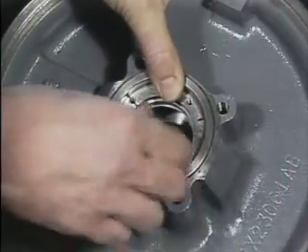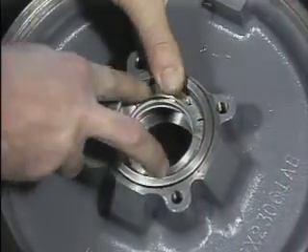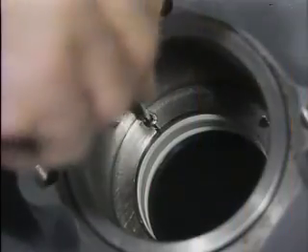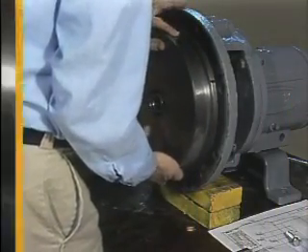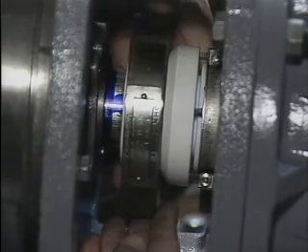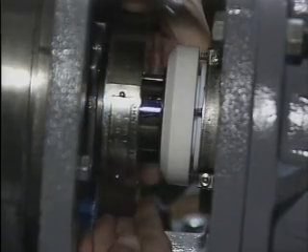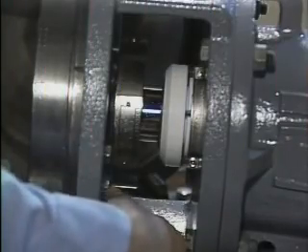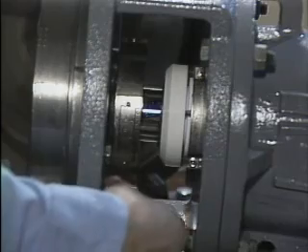Now the back plate is prepared for installation. First, the bushing is inserted into the stuffing box and secured with a screw. Then the back plate is installed on the pump frame. Next, the gland plate is slid into position, and the cap screws that hold it in place are tightened. Then a feeler gauge is used to measure the gap between the gland plate and the back plate.